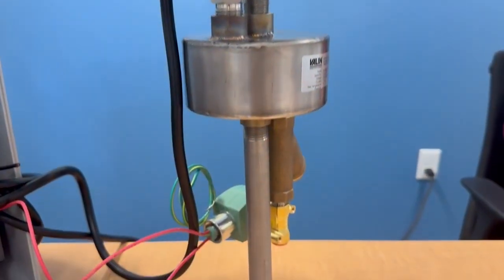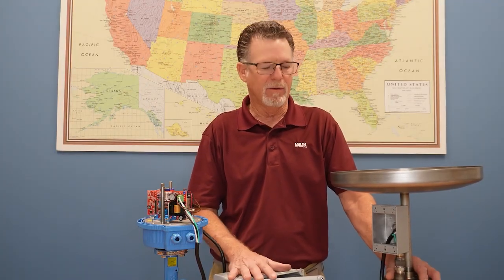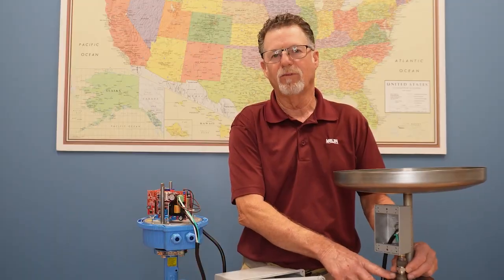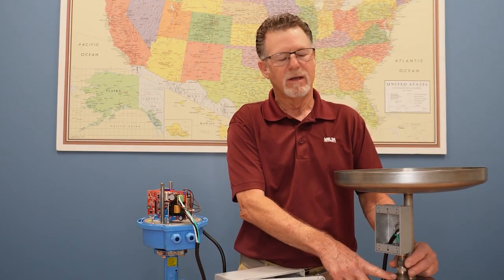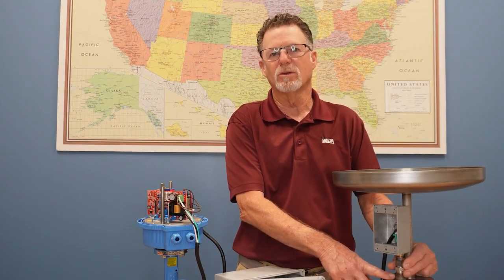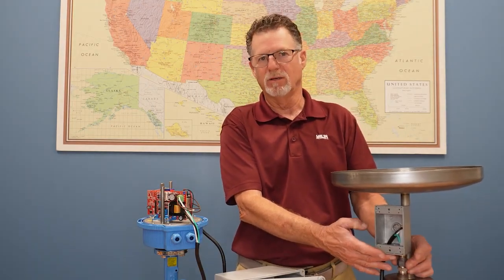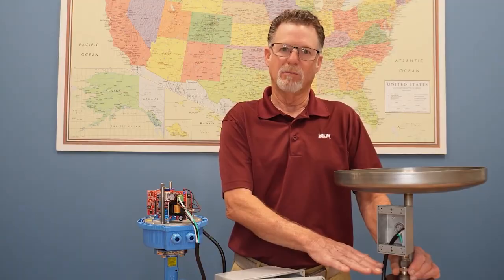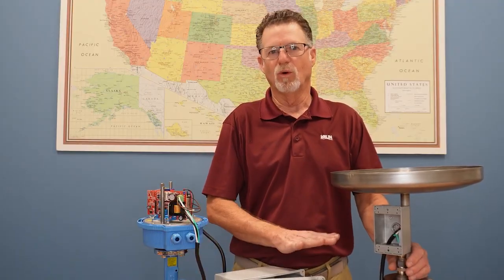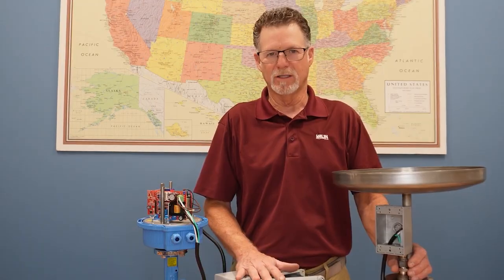The old units were a Joe Bell carbon steel enclosure, and those had floats. They actually had a mechanical float that rode up and down. In 2000, we started making it all stainless steel. We did have a green Pepperl+Fuchs sensor in the first rev. They didn't work out so well, so we pretty rapidly switched to the stainless steel probe, Luminite. So you'll see different rev numbers and different products, but the old versions are not compatible with this pilot station. So if you find any of the old units out there not working, you're going to have to upgrade the whole system with a new rain switch and new pilot station.